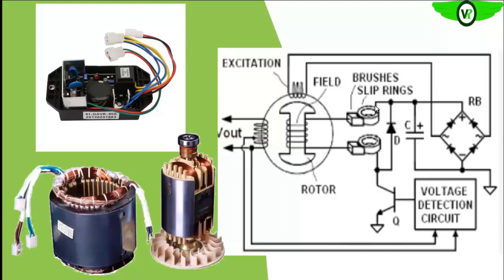Like we said earlier, you have identified this to be the positive and the negative going to your main field, okay? So when you place your red probe here and your black probe here, you will have a reading. But if you reverse it, you are not expected to have readings. If you have a reading, it means that the diode assembly in the AVR is faulty. Then the phase to phase, you also don't expect to have a reading. If you have a reading on the phase to phase, which is this particular wire, it means that your diode is shorted somehow, okay? It means that your AVR is not functioning properly.